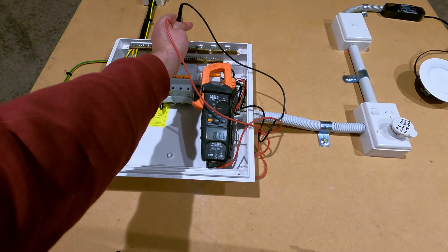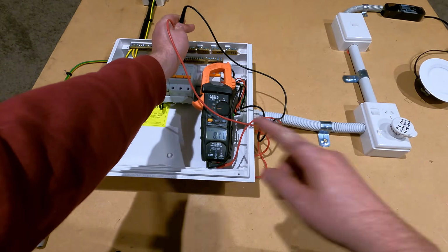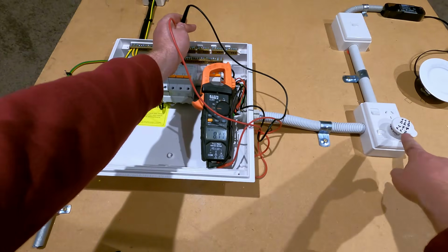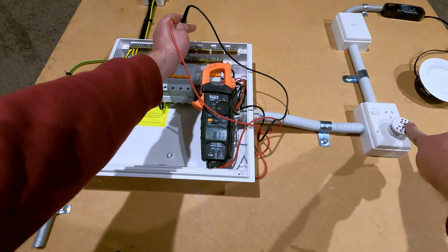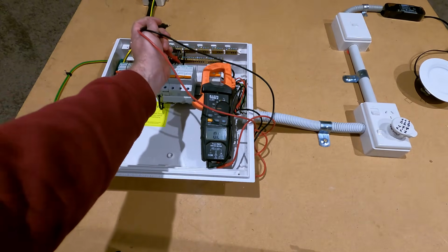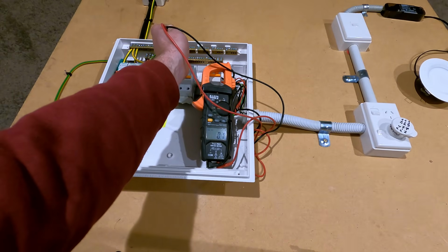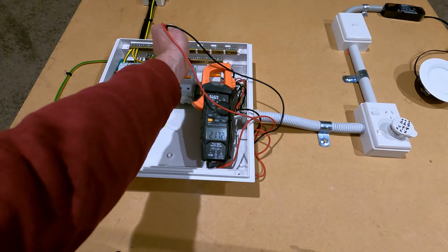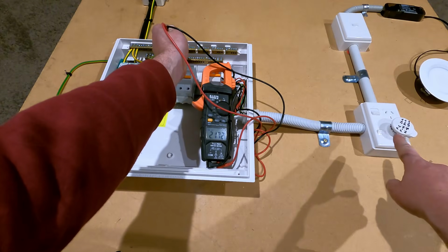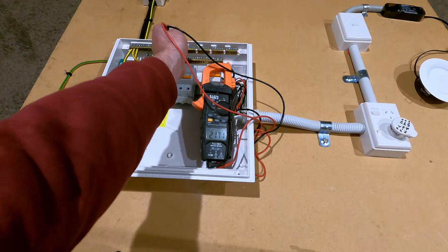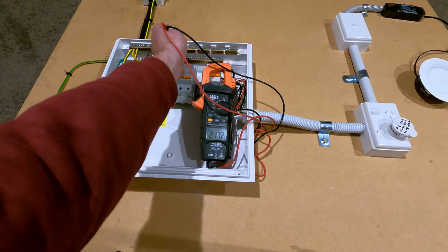And as you can see, we've got 8 kilo ohms. So phase to neutral, 8 kilo ohms. Phase to neutral, 8 kilo ohms. Next we'll do phase to earth. Here we've got 2 kilo ohms. And if you can see on the plug top over there, phase to earth is 2 kilo ohms.